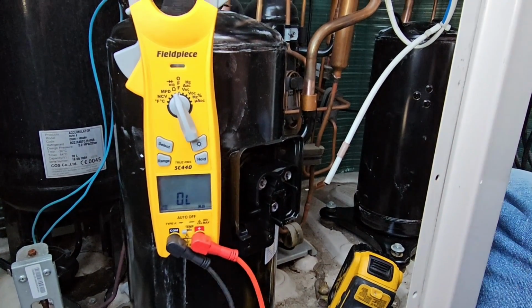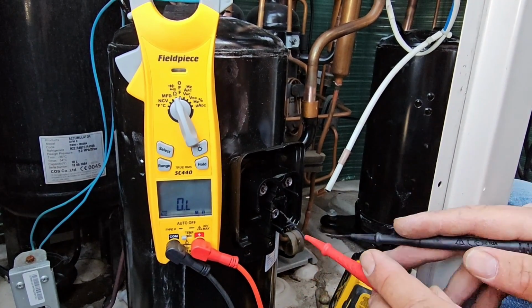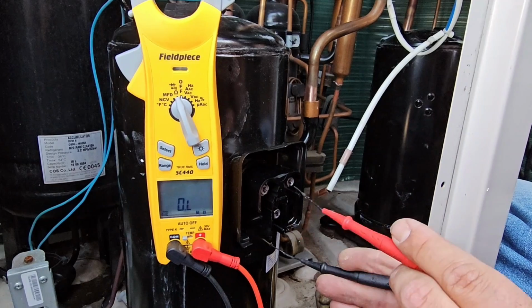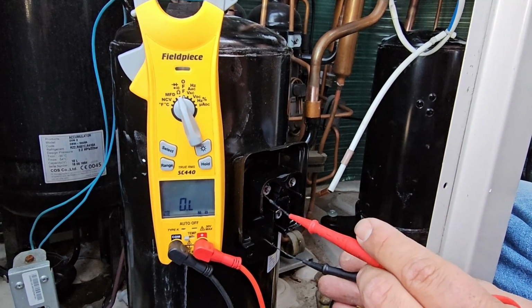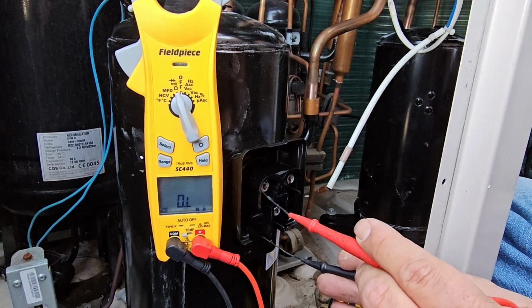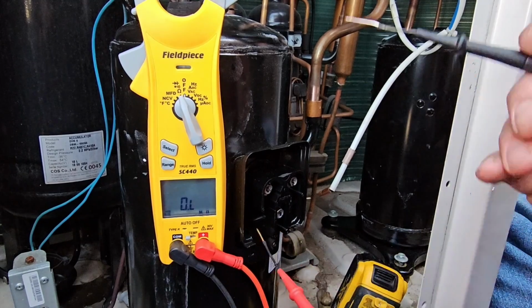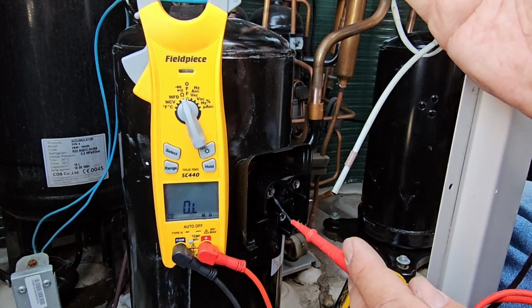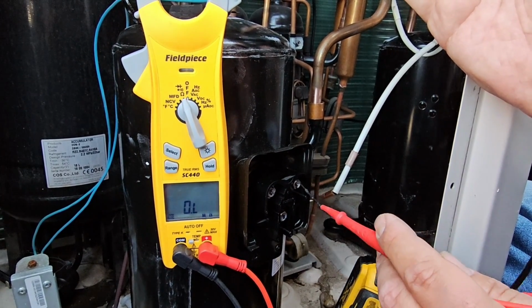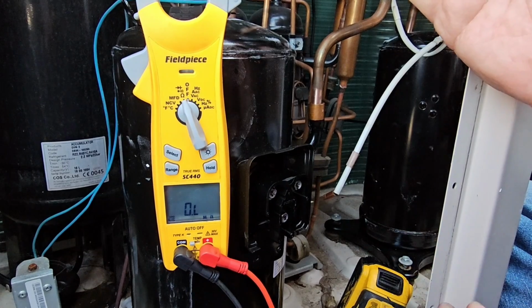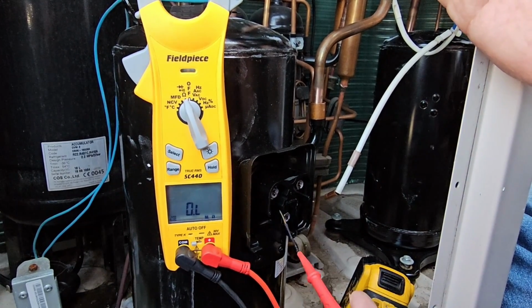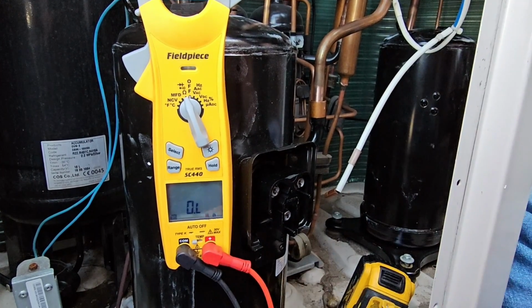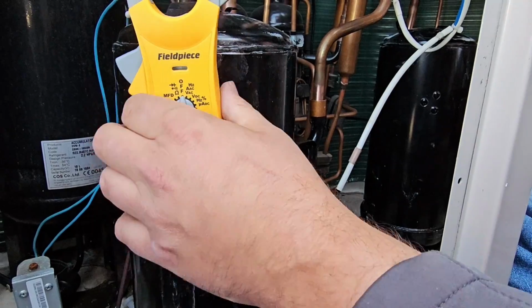Let's turn our meter to ohms. Let's check the new compressor from each winding to ground. And we got no reading, and that's how it should be. Now I'm going to go from the copper to each winding. Okay, so I went from the shell of the compressor to each winding. I went from the copper to each winding. Before we had a reading, now it's open line, open OL.